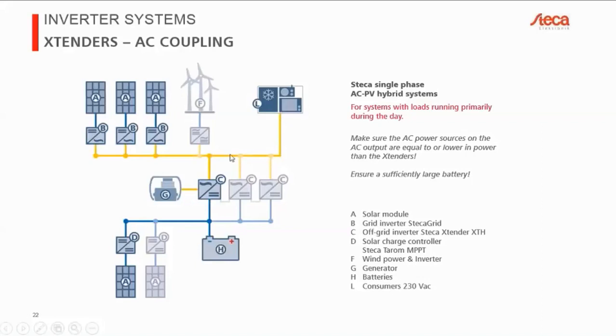But on the same, let's call it a microgrid that you've just created from your inverter, you can also connect grid inverters. They will convert the DC energy from your PV modules to AC, and they will directly power your loads as a first priority, and as a second priority, if you have excess energy, that energy will be rectified by the Xtender and charged into your battery. So even though the Xtender doesn't have a direct PV connection, you can use the AC output to connect grid inverters in an off-grid environment.